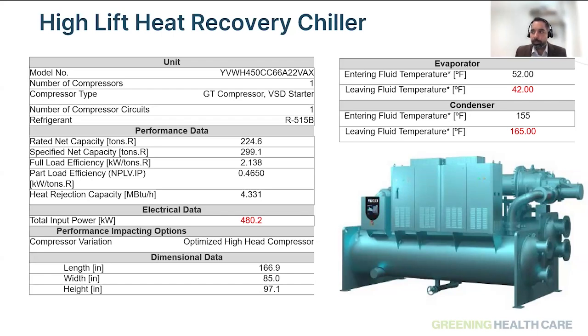I have Robert Larson from JCI joining us on the technical side to help us with this. Robert, thanks for joining us this afternoon. One of the questions that we generally get asked with these heat recovery chillers: we understand it's easy to put in on a new construction because you can size your heating and cooling loops for the low temperatures, whereas in existing buildings it gets complicated because most of your heating coils and terminal units are all sized for hot water loops, right? And the question people are asking is, if we can't have a heat recovery chiller that produces hot water enough to feed those loads, then when the boiler loop goes to higher temperatures, the low temperature heat recovery chiller doesn't work.